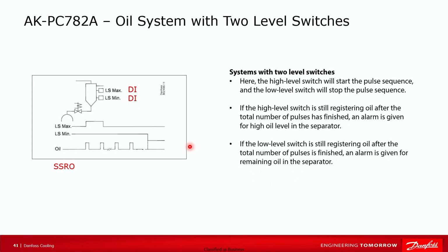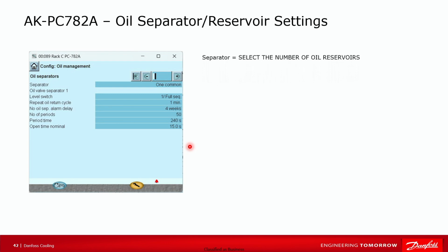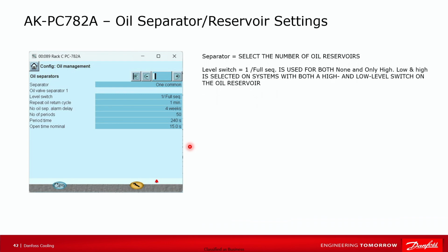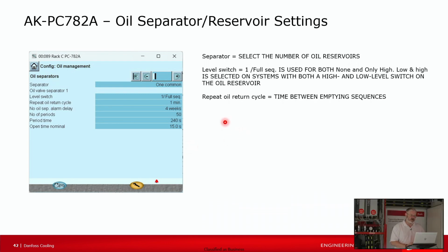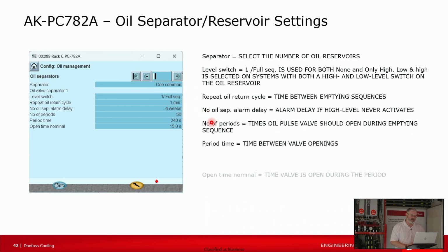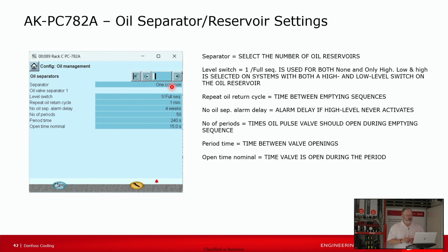And then the third option, which is more common than you'd realize, is there's no level switch. So basically it's all done on timing, and it actually works pretty well. What we would do in that scenario is define that we have one separator, and then we would physically jump a high level switch with a wire jumper on an input that stays in there forever. And that initiates our emptying sequence at all times. And then you can define from there how often you want it to empty.